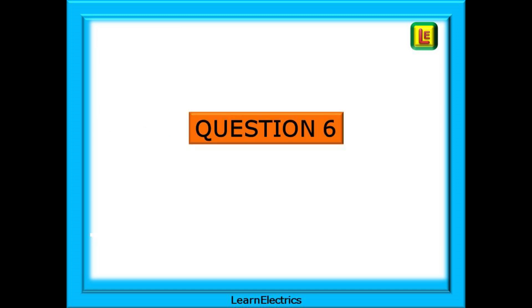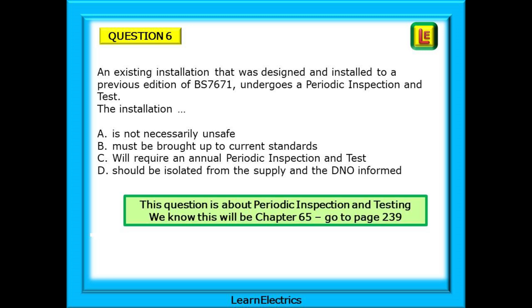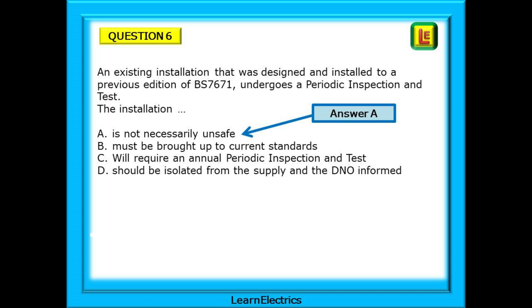Question 6: an existing installation that was designed and installed to a previous edition of BS 7671 undergoes a periodic inspection and test. The installation — and four possible statements to complete the sentence. This question is about periodic inspection and testing, which is chapter 65. Going to page 239 to find the answer, lots of useful information is often tucked away in notes and small print — they make excellent question material for exam setters. Regulation 651.2 note 2 gives us the answer. Our answer choice is A: is not necessarily unsafe.